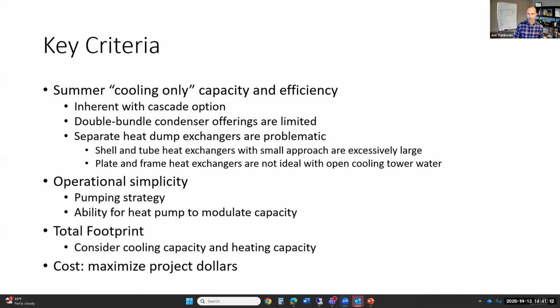Another important factor is the cooling capacity. Some of those newer machines weren't really an in-kind replacement of some of our aging chillers, whereas the Cascade option did allow that. So it was another factor pointing us in that direction.